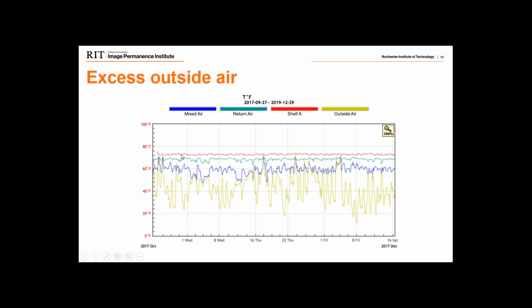So we're probably at about 72 degrees in the space, and then we return about 68, so there's a little bit of a temperature loss. So with that temperature loss, it's now pretty cold outside, and it's an unoccupied collection space. And you can see here, we're actually using a fair amount of outside air and losing some temperature. I lost my cursor there. Losing some temperature with that. So this air, this blue line, to go back out to the collection space has to be heated up to about the red logger's condition. So all this is work that has to be performed to make it usable for the collection. Again, it's an unoccupied space.